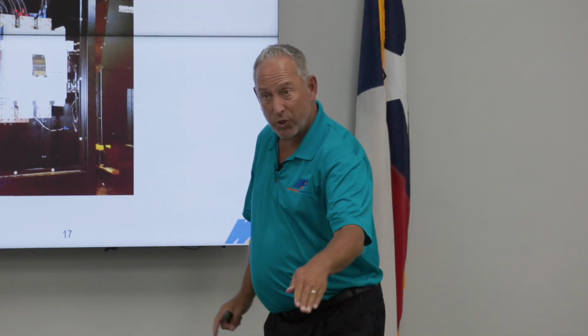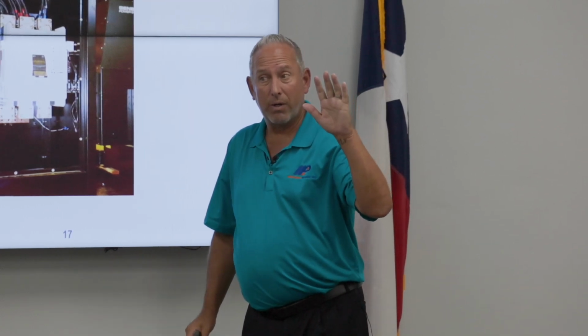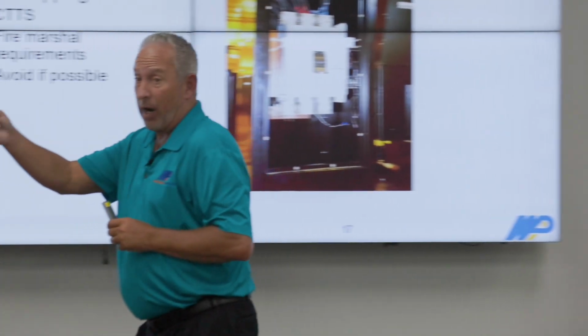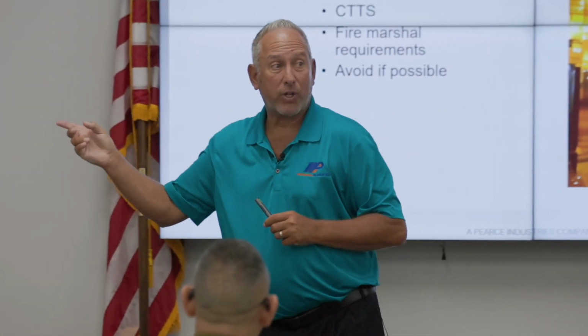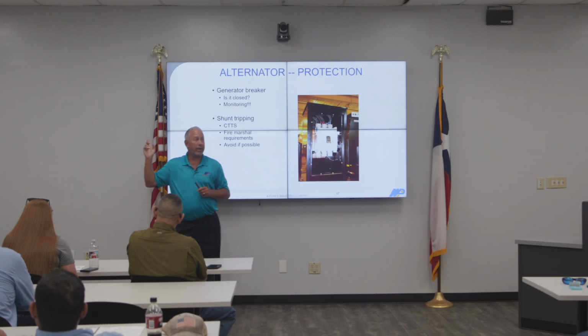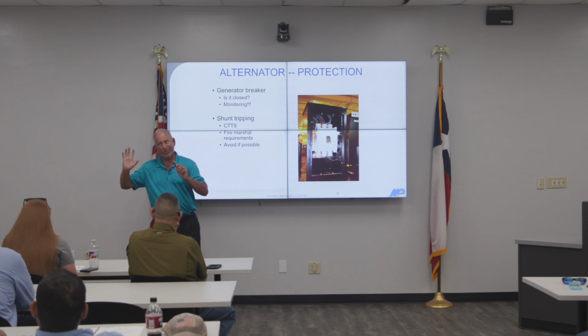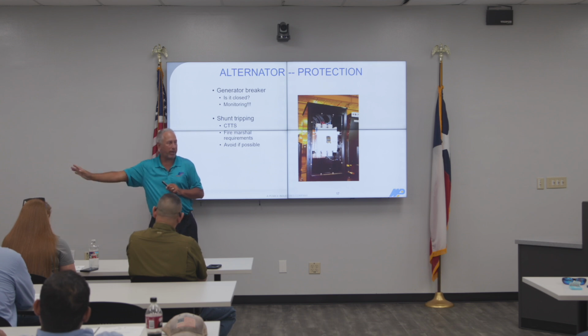So you put a voltage to it and it trips the breaker. The application for that would be, a lot of times people will do it on fire suppression. So there's a fire in the building, and there's different philosophies with this, right? Sometimes there's a fire in the building, they want to secure all power in the building. Fire alarm goes off, it trips the breaker.